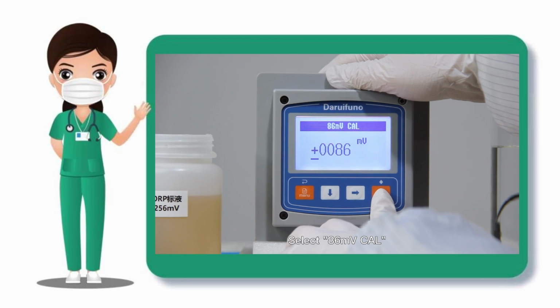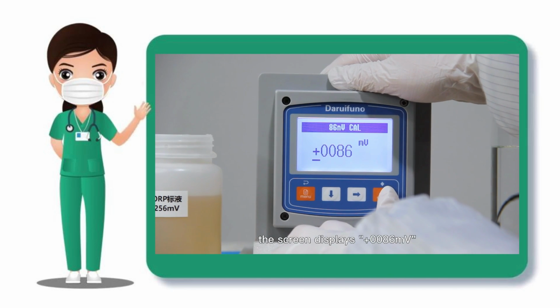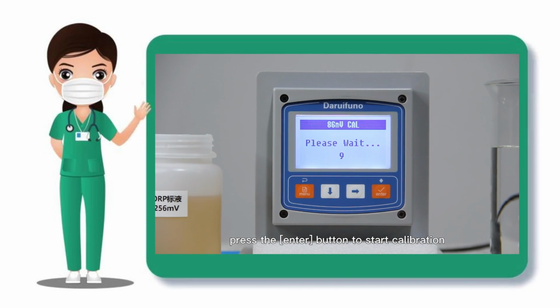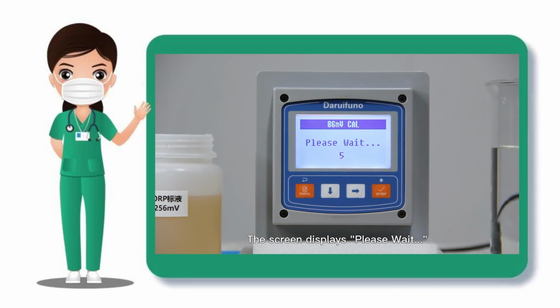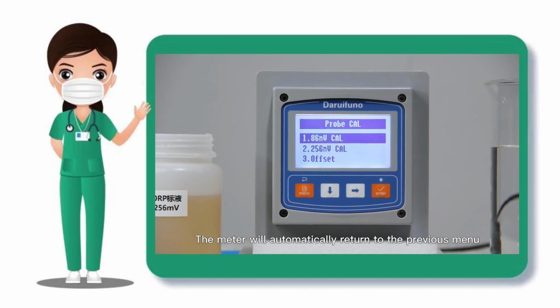Select 86 mV cal. The screen displays plus 86 mV. Press the enter button to start calibration. Gently agitate the sensor. The screen displays please wait. When the screen shows success, the calibration is complete. The meter will automatically return to the previous menu.